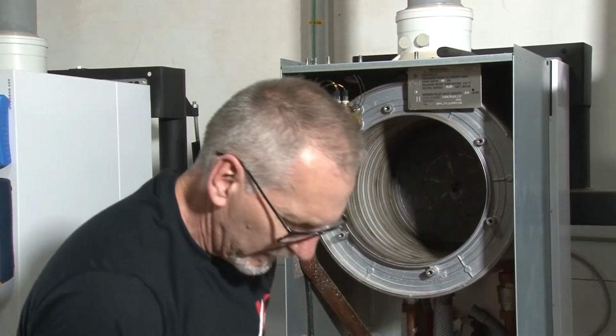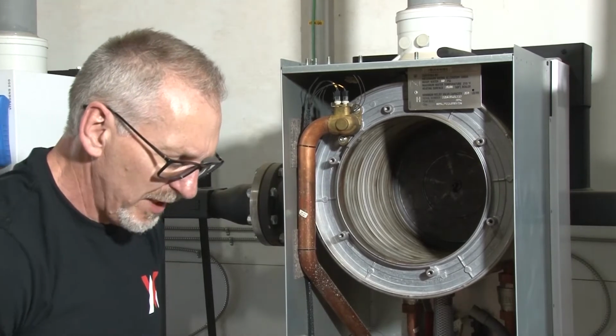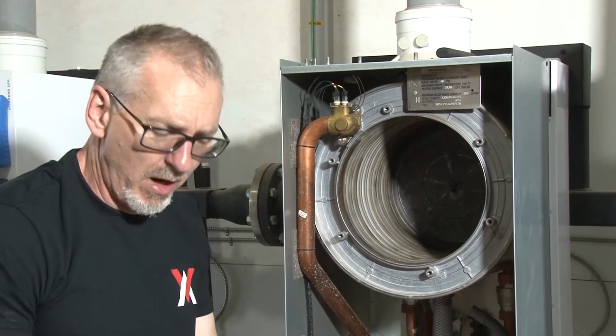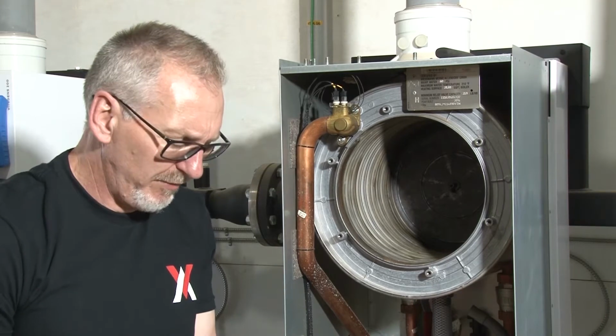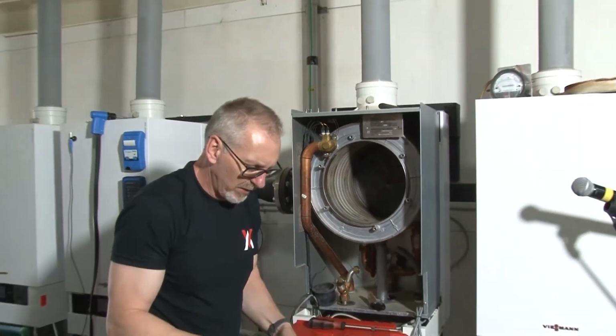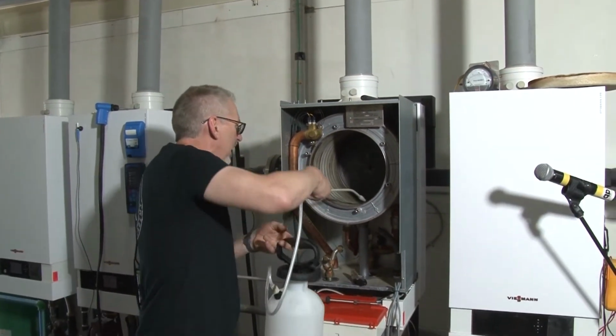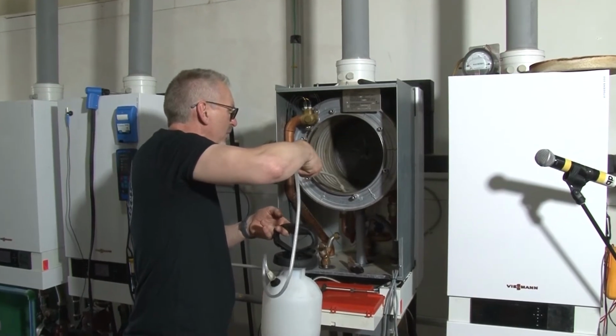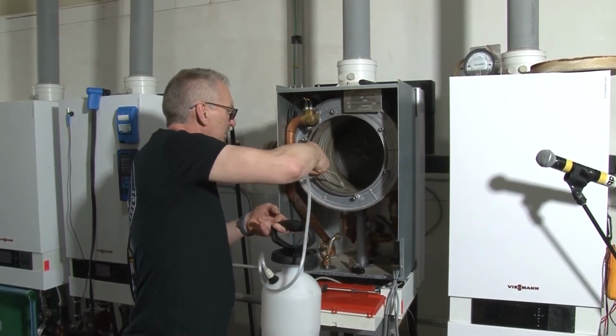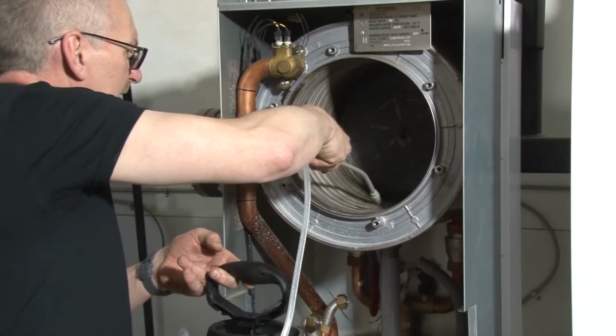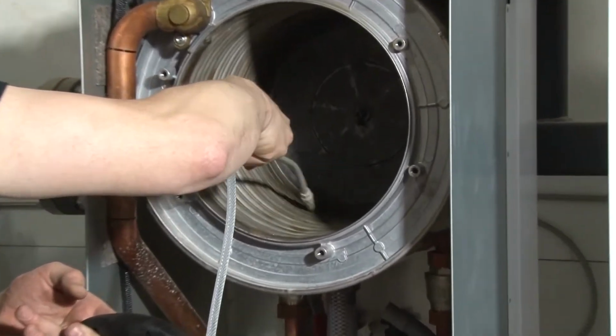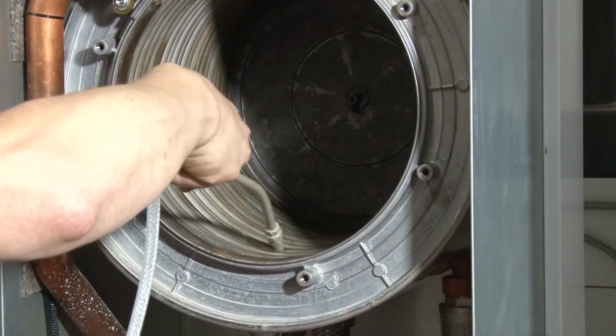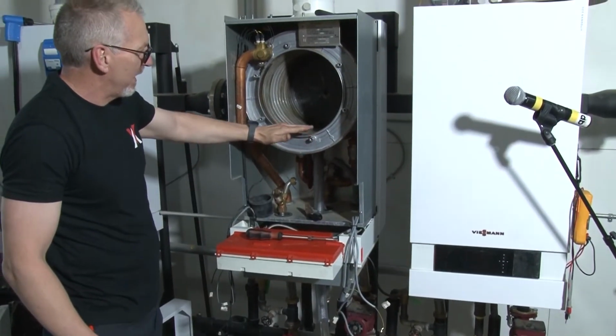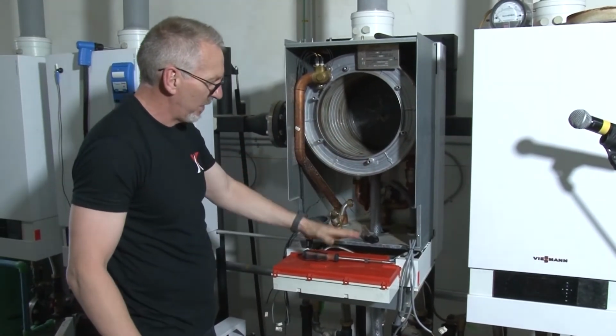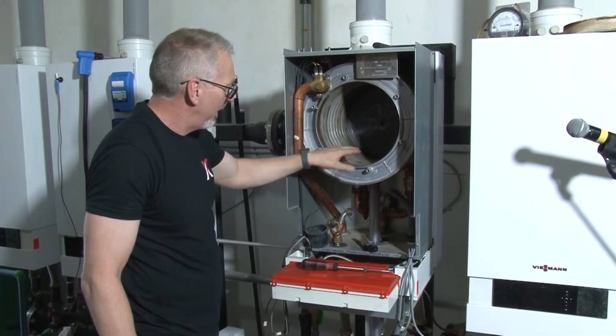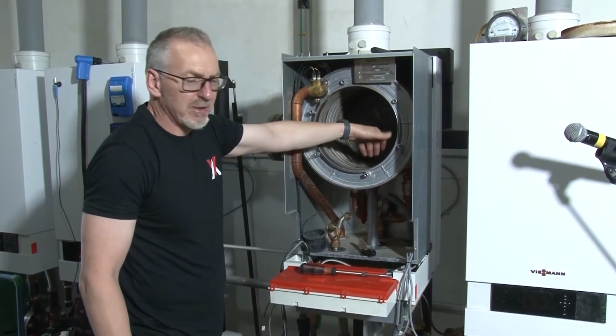And like I say, a lot of times if your boiler is fairly clean, all you really need is hot water. The hotter the water, boiling water is really good if you can handle it. But a nice hot water, and basically we just kind of flush it in that heat exchanger, just pour it in. This has some citric acid in it, which kind of escalates the cleaning a little bit. Just basically gives us a bit more surfactant that's going to basically bubble up there. And I noticed the water was coming up and coming out the front of the boiler. Obviously I don't want that to happen because of the control in the front. But that's telling me the gaps are really plugged.